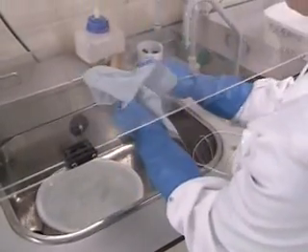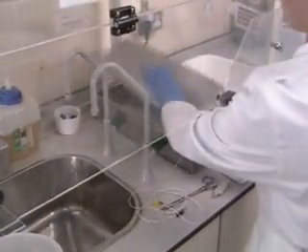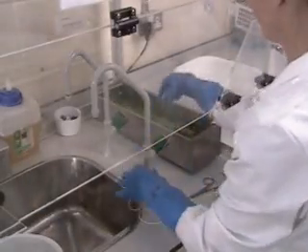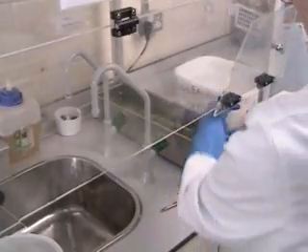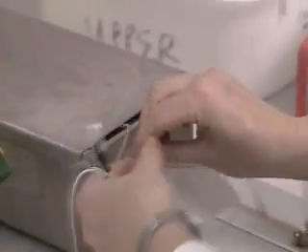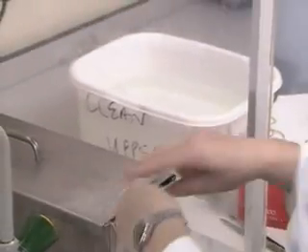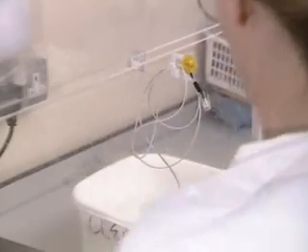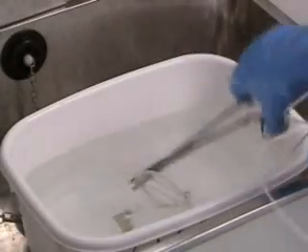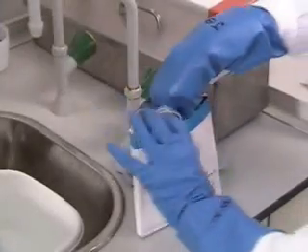When a multi-use catheter is used, it must be washed immediately in detergent and warm water, dried, and then placed in a sterilizing solution, such as glutaraldehyde, for the indicated period, generally 10 minutes. Care must be taken not to wet the connector. The reference electrode and lead can be washed, dried, and then wiped over with an alcohol swab. Sticky residue from the tape can be removed using acetone or something similar. Finally, rinse the catheter thoroughly in water to remove all traces of sterilizing solution, dry, and store, ready for reuse.